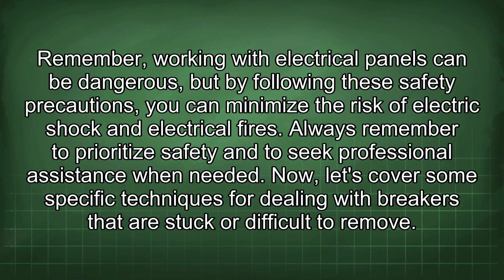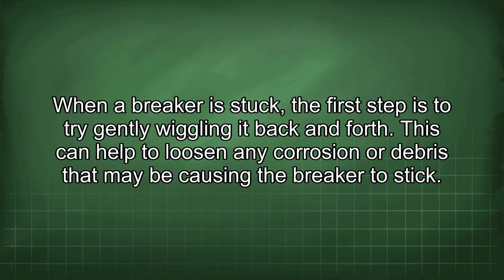Now, let's cover some specific techniques for dealing with breakers that are stuck or difficult to remove. When a breaker is stuck, the first step is to try gently wiggling it back and forth. This can help to loosen any corrosion or debris that may be causing the breaker to stick.